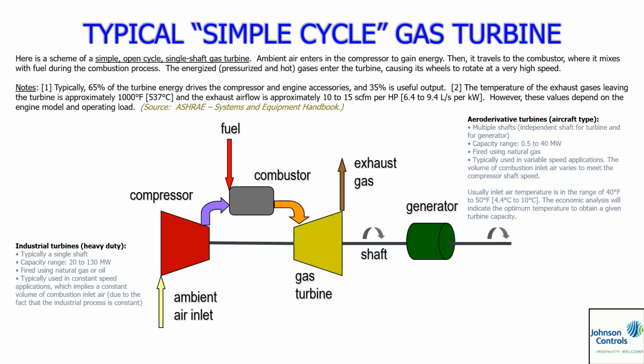Okay, so a couple of notes, and this is per ASHRAE, our sister organization, Systems and Equipment Handbook. Typically 65% of turbine energy drives the compressor and engine accessories, which leaves only 35% for useful output. That's a very important item to remember. The temperature of the exhaust gas leaving the turbines is usually in the 1,000-degree range, with the airflow of 10 to 15 standard cubic feet per minute per horsepower. Now, these values depend on the engine model and different operating load that you're dealing with, but that's just some rules of thumb.